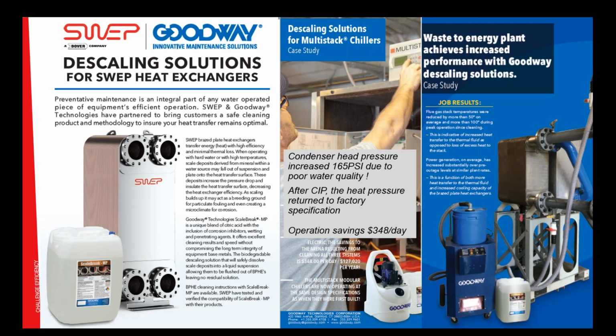close the system down. And after about 24 hours of cleaning in place, the whole system returned to factory specification. It was completely restored. So there was enormous fouling, and it was completely restored in one day. And the economic savings of having a clean condenser, with the head pressure reduced by 165 psi, the saving was $348 a day.